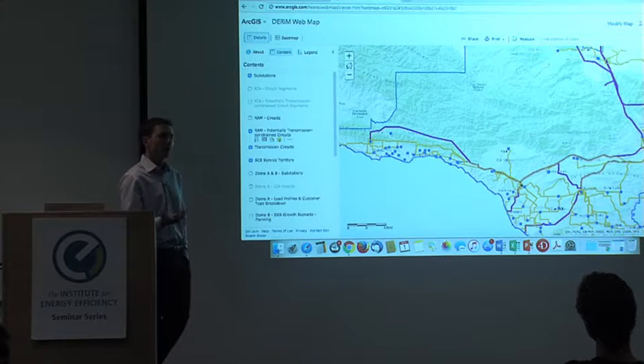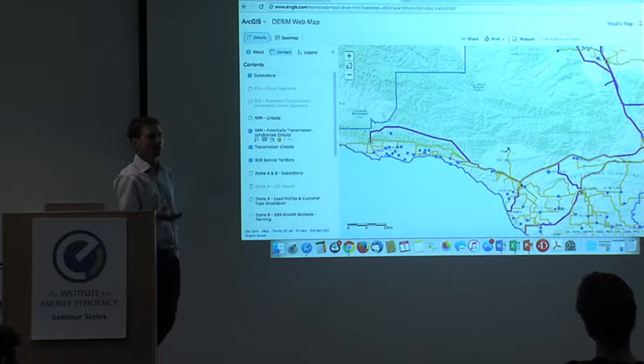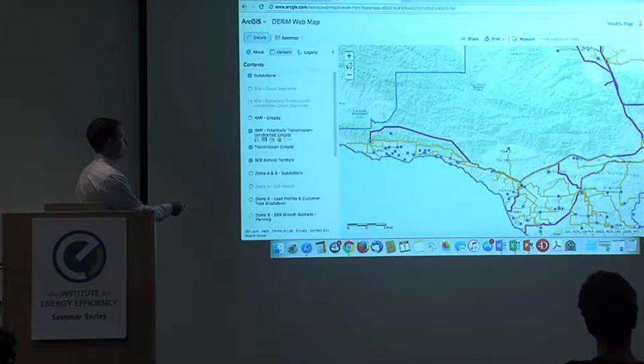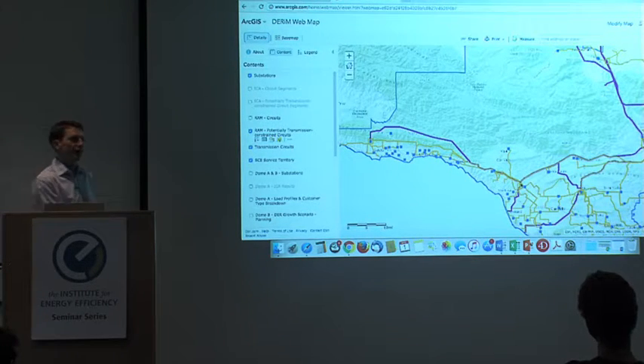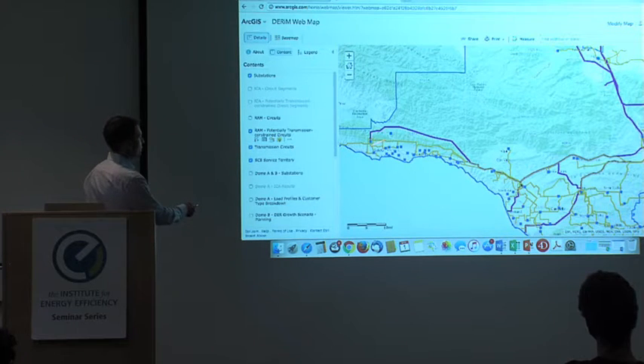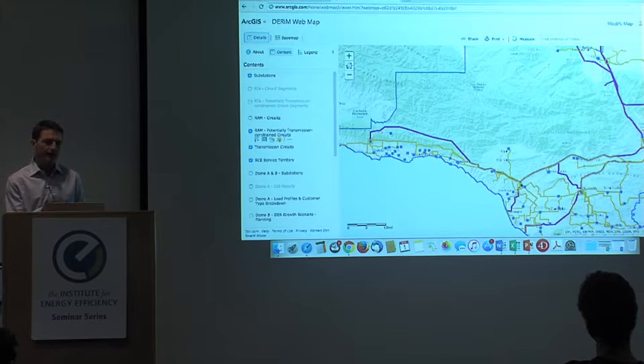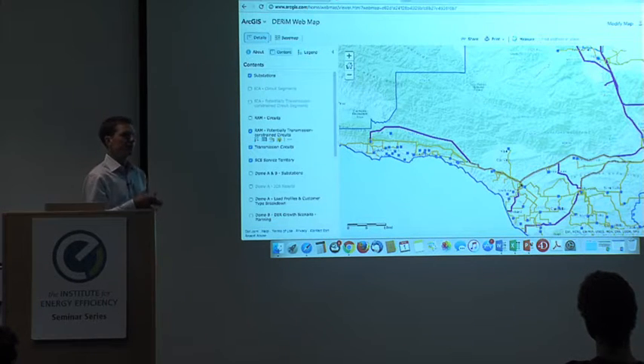It's what we call normally open. They're tie lines, so we wouldn't typically be served all the way from Ventura by that system. We'd be served by the 220, and then partially served by the 66 here, which would serve the other part of our territory from the other direction. The reason for that is, on a peak day, there's too much load for this 66 kV circuit to carry. That's the biggest problem we face in terms of power reliability, since you've got the Whittier fire territory here and the Thomas fire territory here.